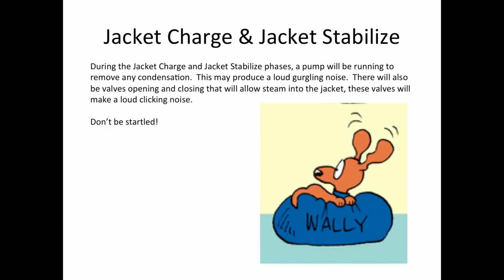Now, during the jacket charge and the jacket stabilize phases, a pump will be running to remove any condensation, and this may produce a rather loud gurgling noise, and there are going to be snapping sounds as valves open and close that are allowing steam into the jacket to maintain its temperature or the necessary pressure. Don't be startled by this very loud clicking noise that these valves are making.